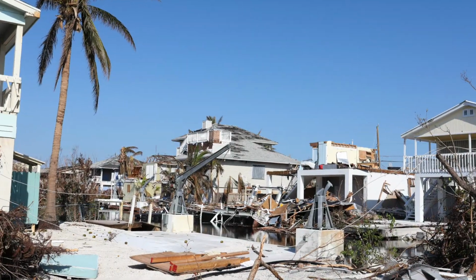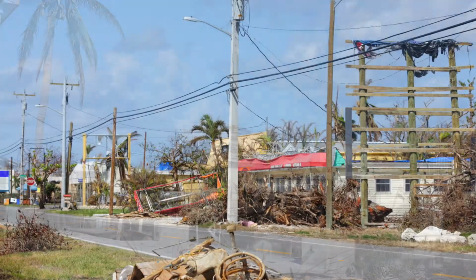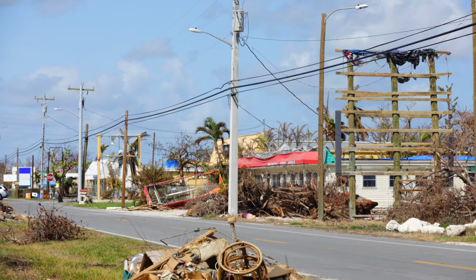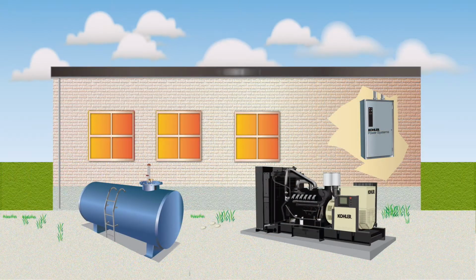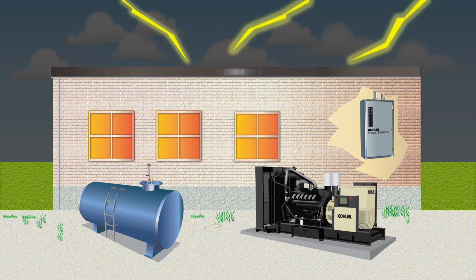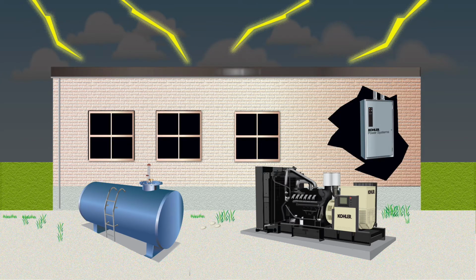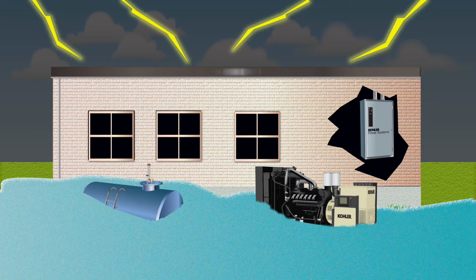After both storms, there were widespread power outages, and in many areas there was no power for a few weeks. In addition to the utility power failing, FEMA also investigated why many standby generators failed to start or provide sustained critical power to healthcare and communication installations after the storms had destroyed the locally distributed utility power. One of their conclusions was how exposed generators and their fuel supply were to rising floodwater brought on by hurricane storm surges, heavy rain, and flying debris.